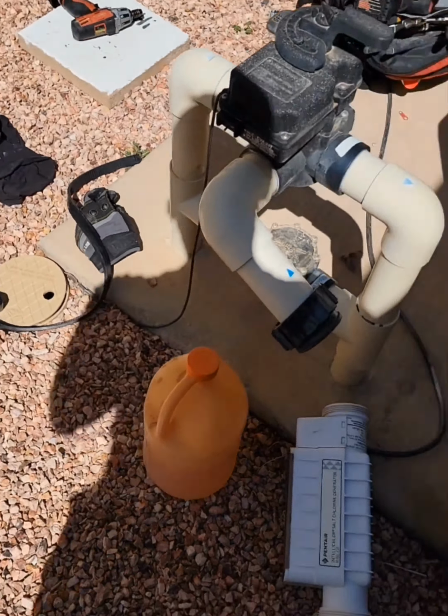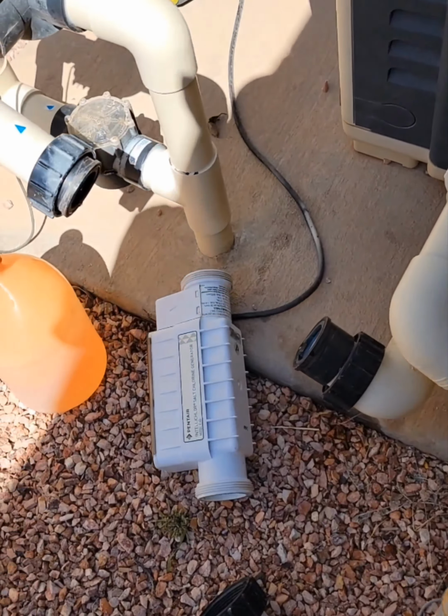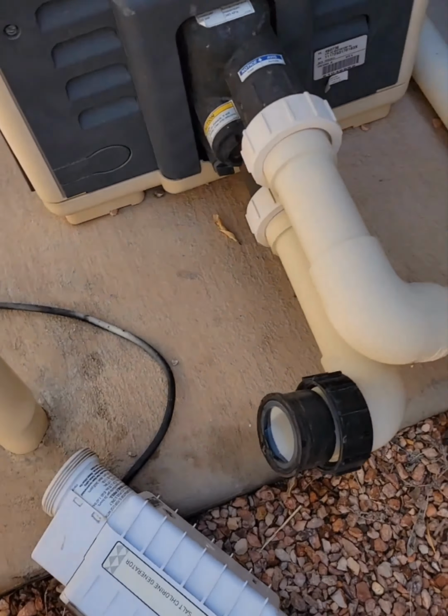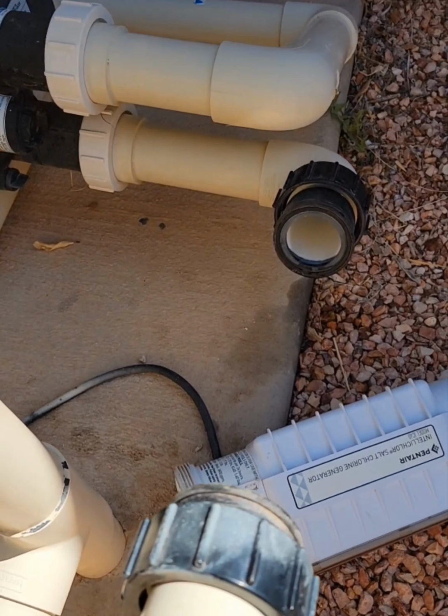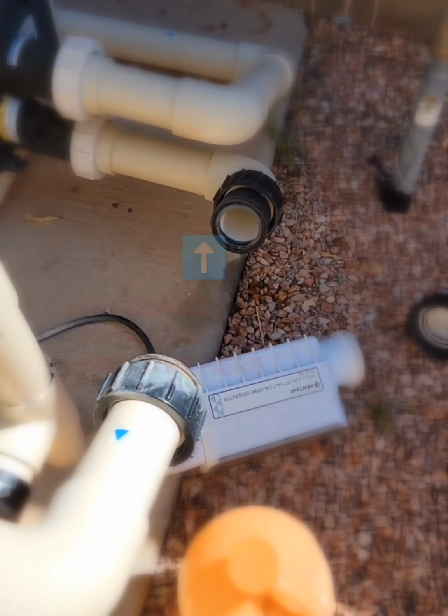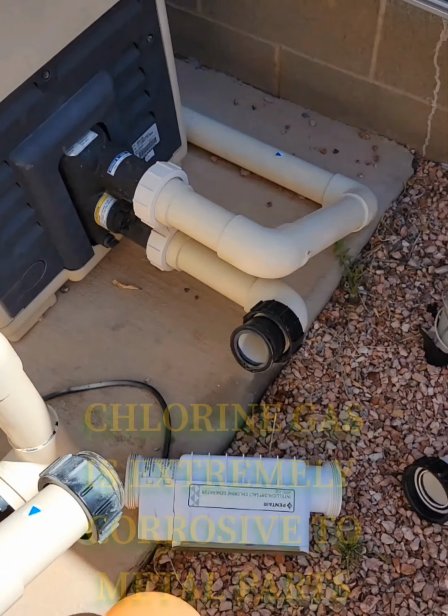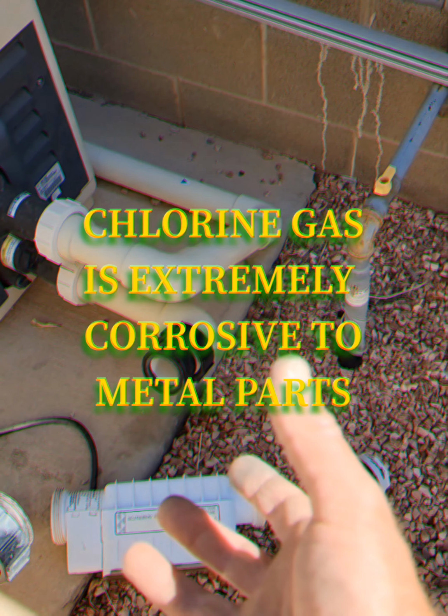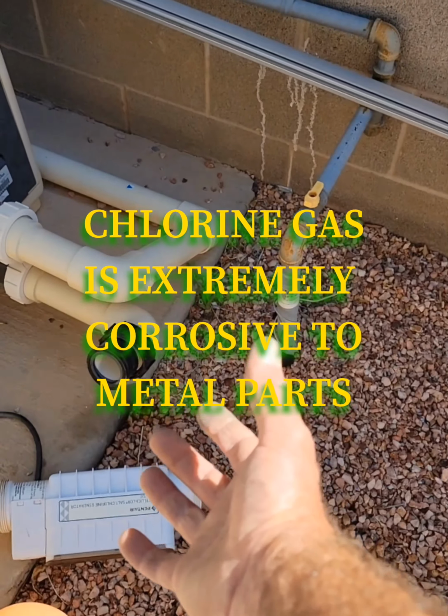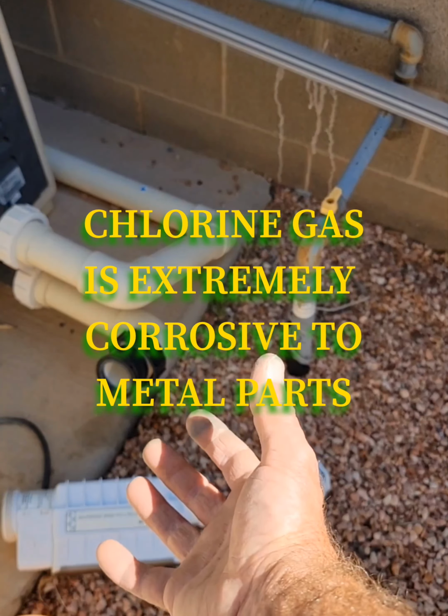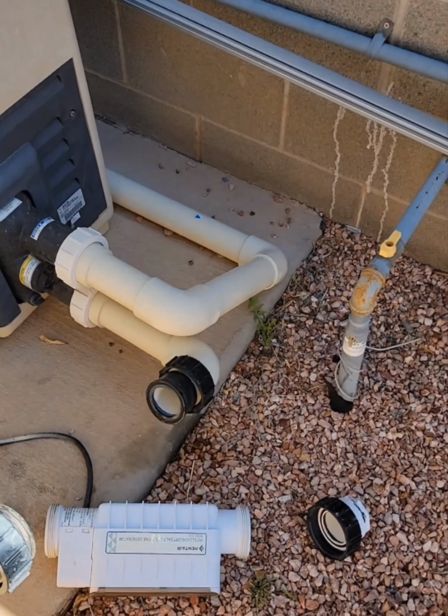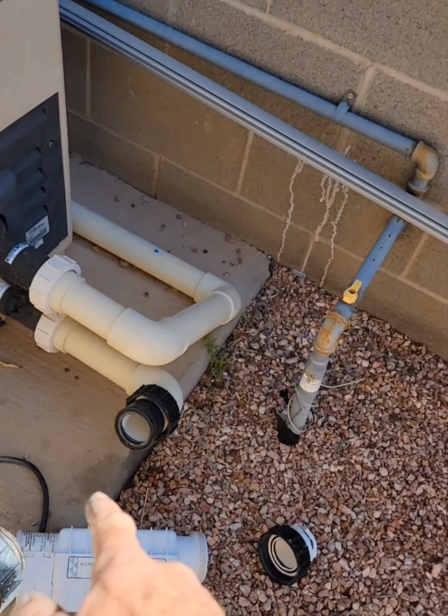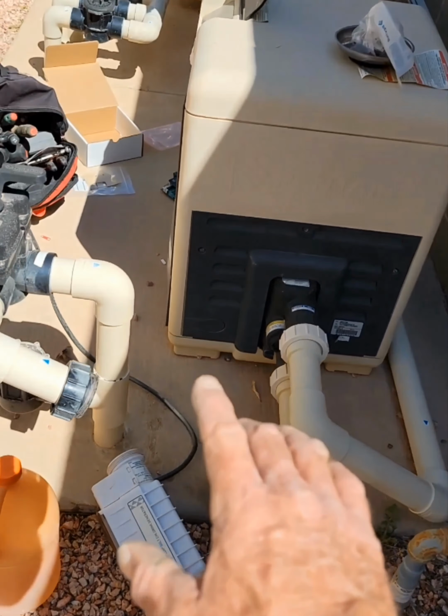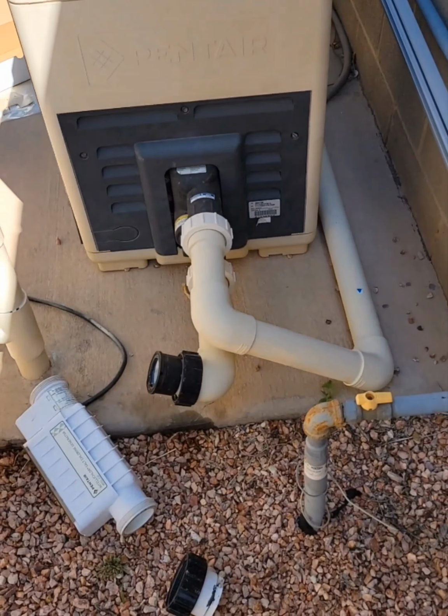But then I noticed that they don't have a check valve after the salt cell there. So when the unit shuts off, the corrosion that's generated when the salt cell is working just flows right back into the heater and corrodes everything. So that's what did that. And I imagine the heat exchanger inside there also looks really bad.